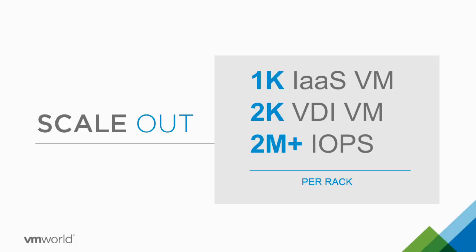What do you get out of such infrastructure? You get a very scale out kind of a model. You can start at very small infrastructure like 8 server nodes with some switches, and incrementally add 1 server at a time to scale out. And in a rack full of servers, we assume 24 2-socket servers in a rack, because most of the enterprise IT is limited by the amount of power they can supply to one rack, to about 12.5 to 13 kilowatts. Within that power envelope, we can support 24 servers plus switches.